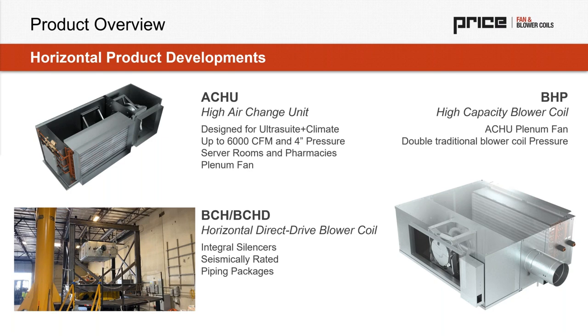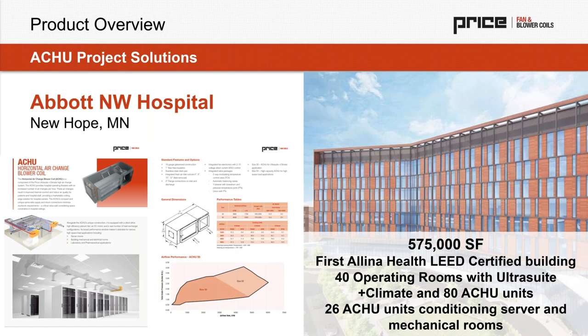We started to learn a lot about plenum fans because of the product on the left, which is called our high air change unit. And it was actually generated and created as a fan coil for operating rooms. And in particular, this was for the Abbott Hospital in Minneapolis, just outside of Minneapolis in New Hope, Minnesota. And this product was a requirement from the hospital because they actually wanted to run their operating rooms at 60 air changes rather than the code required 18 to 24.